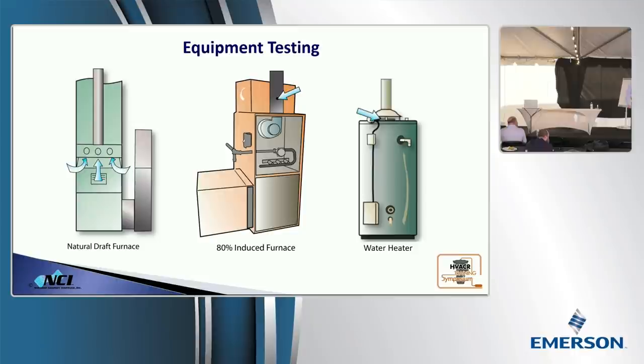A lot of technicians will freak about this because you can't get the analyzer probe down in to the outlet of that heat exchanger on a water heater. They'll freak out because you have to drill a small hole in the hood. It's got a great big freaking hole already in it. What's a little one going to matter, right? But you don't drill holes. We install test ports. And we're doing that to make sure combustion air is accurate. So there's a water heater.